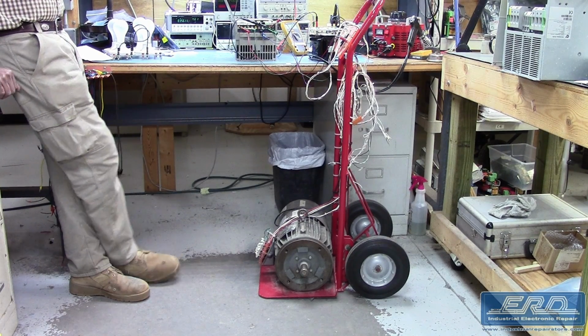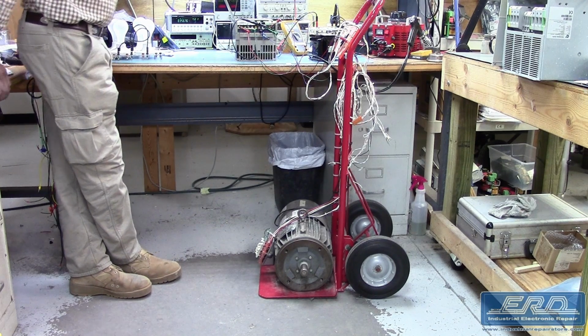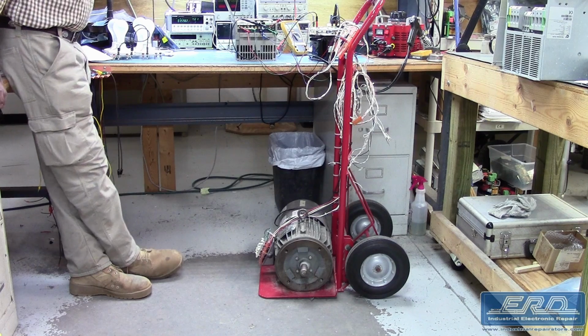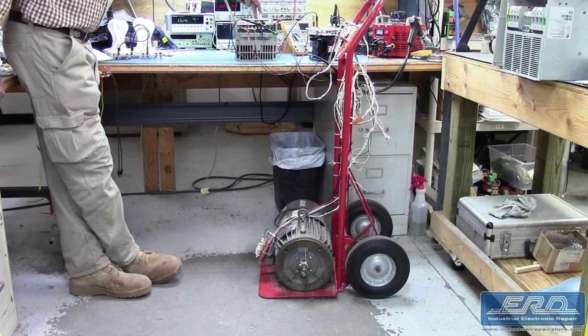These motor controls tend to fail in the main power supply and have damaged boards. We cleaned up the damage, repaired the bad connection, and rebuilt all the other subassemblies before we fully tested the unit on one of our motors, as shown in the video.